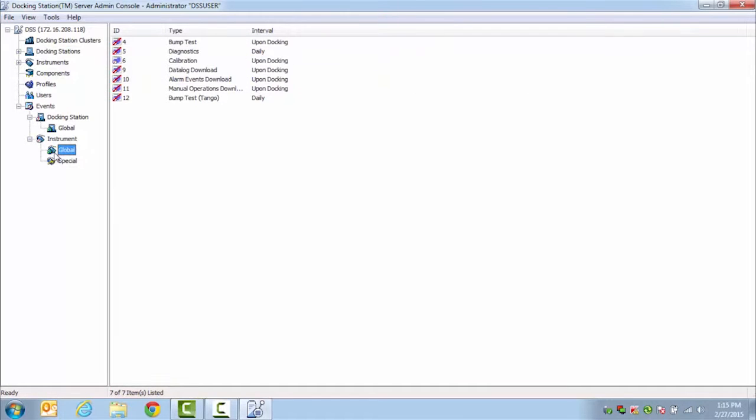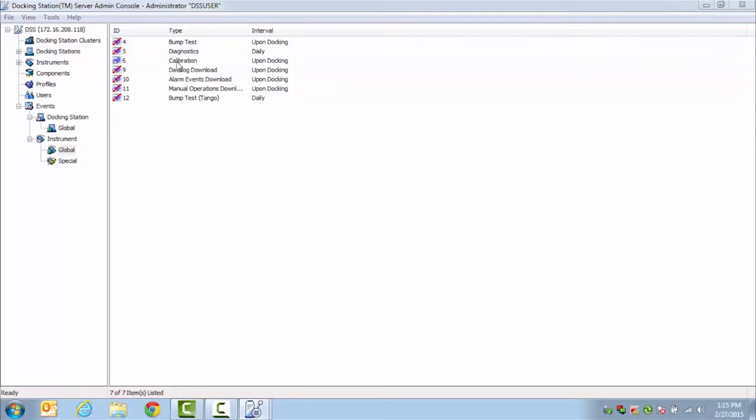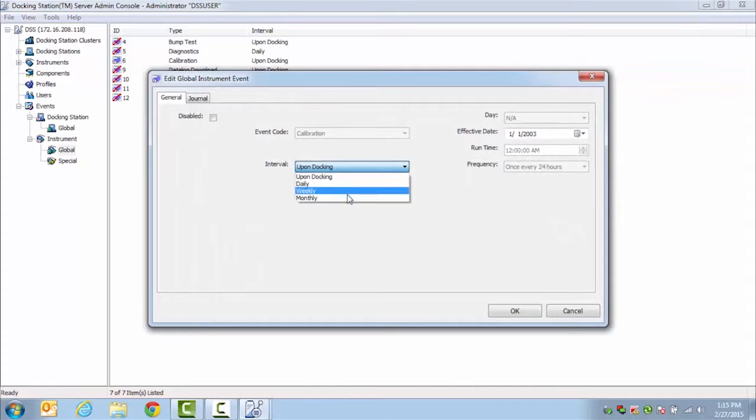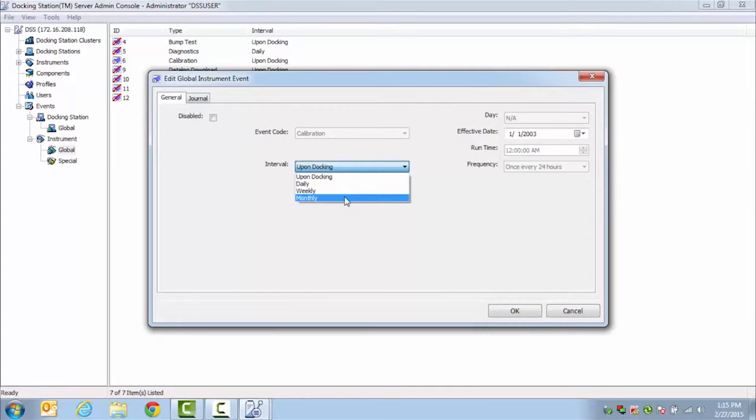When you take a look, you will see all of your different events, and from there, you will be able to change their interval by double-clicking on them and changing when you want them to occur. Per Industrial Scientific's recommendations, calibrations should be done once a month or every 30 days, and bump tests should be completed before each day's use.